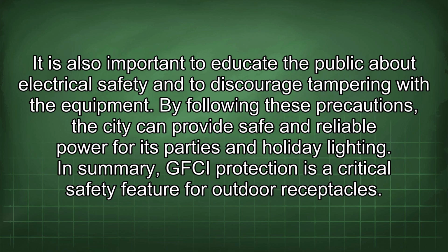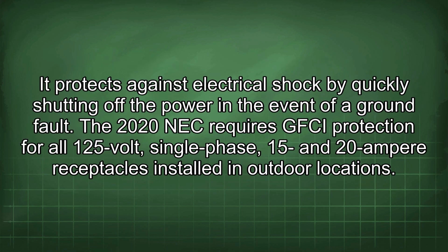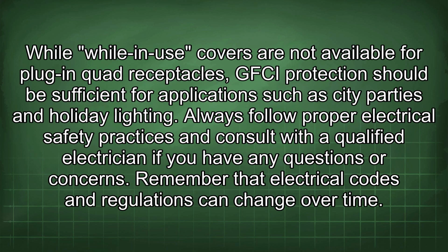In summary, GFCI protection is a critical safety feature for outdoor receptacles. It protects against electrical shock by quickly shutting off the power in the event of a ground fault. The 2020 NEC requires GFCI protection for all 125-volt single-phase 15 and 20 ampere receptacles installed in outdoor locations. While-in-use covers are not available for plug-in quad receptacles, GFCI protection should be sufficient for applications such as city parties and holiday lighting.